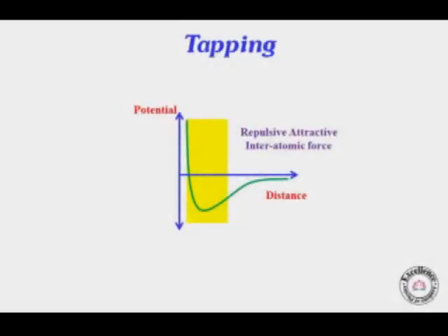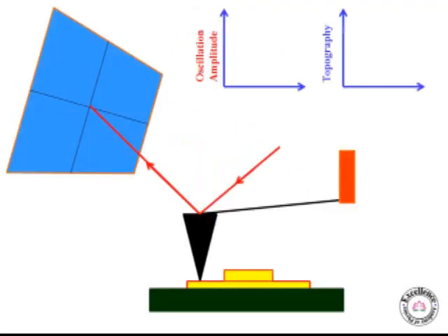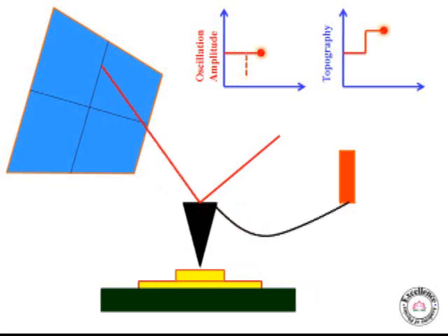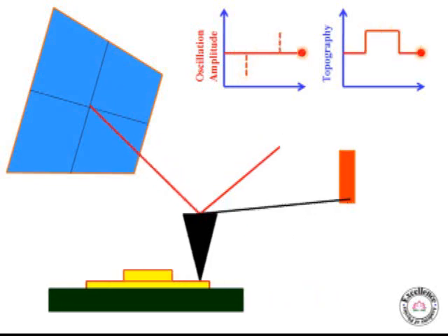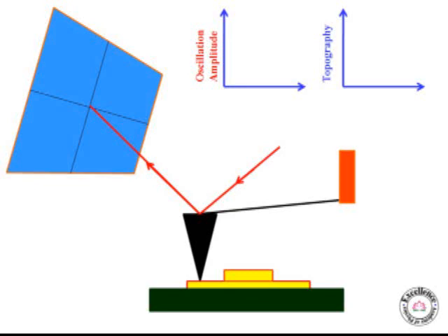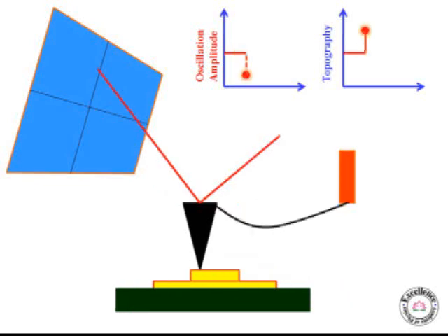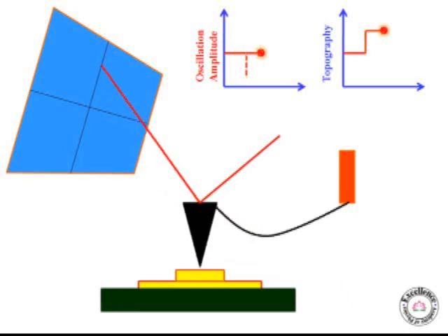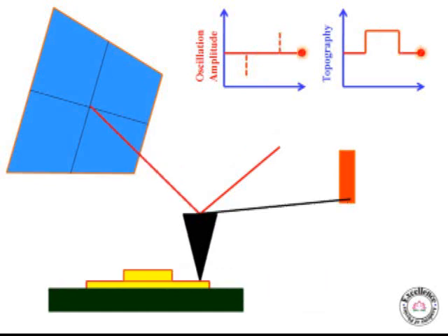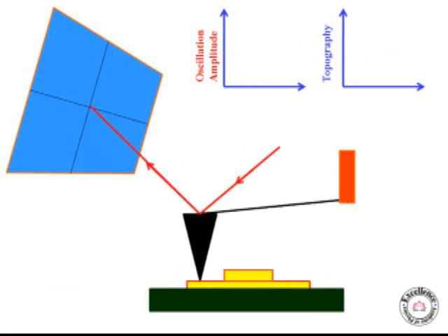Tapping mode is an alternative technique to contact mode. In this case, the cantilever again oscillates just above the surface, but at a much higher amplitude of oscillation, at about 20 to 300 kHz. The bigger oscillation makes the deflection signal large enough for the control circuit, and hence an easier control for topography feedback.